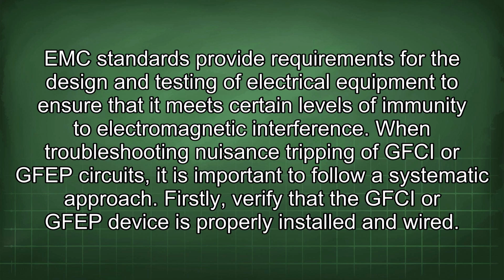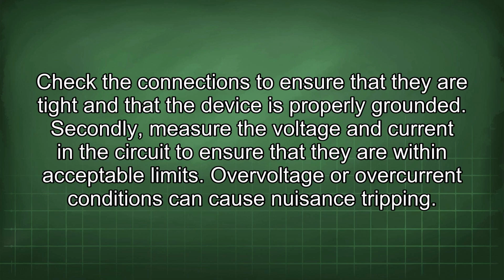EMC standards provide requirements for the design and testing of electrical equipment to ensure that it meets certain levels of immunity to electromagnetic interference. When troubleshooting nuisance tripping of GFCI or GFEP circuits, it is important to follow a systematic approach. Firstly, verify that the GFCI or GFEP device is properly installed and wired. Check the connections to ensure that they are tight and that the device is properly grounded. Secondly, measure the voltage and current in the circuit to ensure that they are within acceptable limits. Overvoltage or overcurrent conditions can cause nuisance tripping.